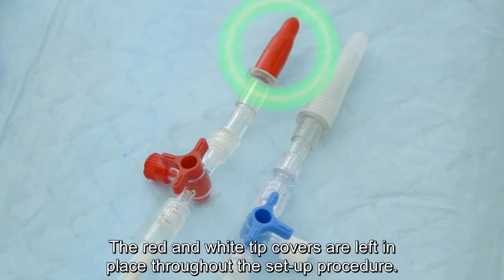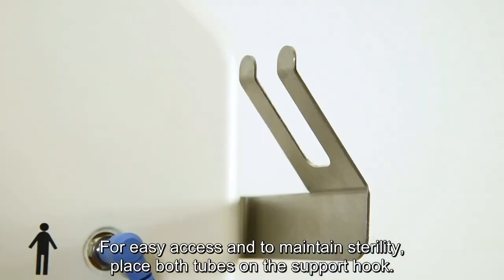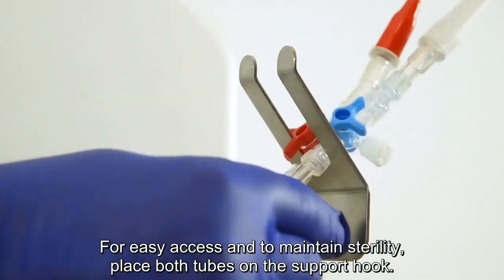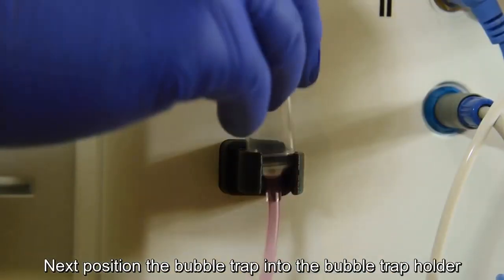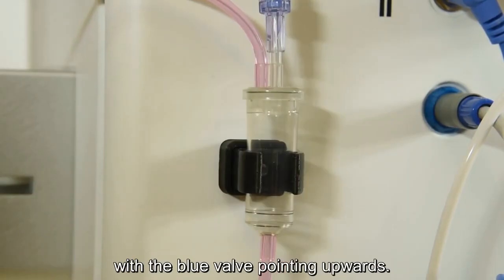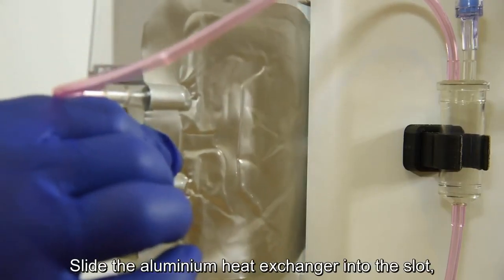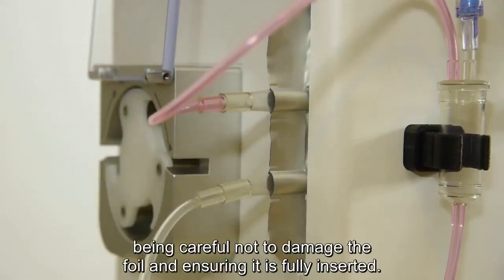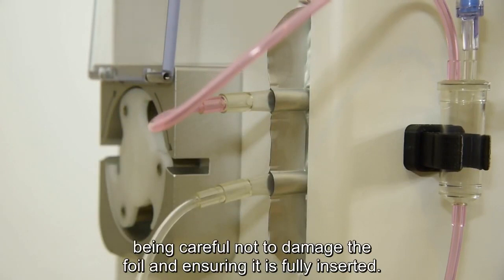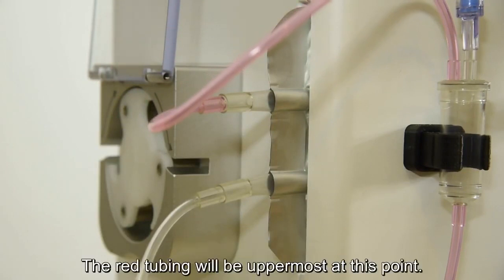The red and white tip covers are left in place throughout the setup procedure. For easy access and to maintain sterility, place both tubes on the support hook. Next, position the bubble trap into the bubble trap holder with the blue valve pointing upwards. Slide the aluminium heat exchanger into the slot, being careful not to damage the foil and ensuring it is fully inserted. The red tubing will be uppermost at this point.